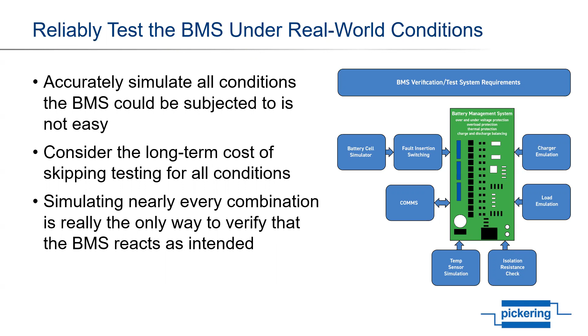The only real way to have the level of confidence required in your BMS system is to take all the stimulus being simulated and build the automated test around it, ensuring that you simulate every combination of conceivable scenarios, ensuring the BMS reacts as expected. As you can see from the diagram, this can include many signals and connections, including battery cells, fault simulation, communication, charging, loads, temperature, and isolation checks.